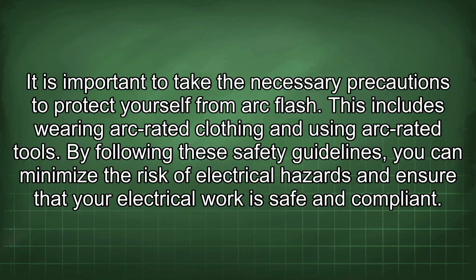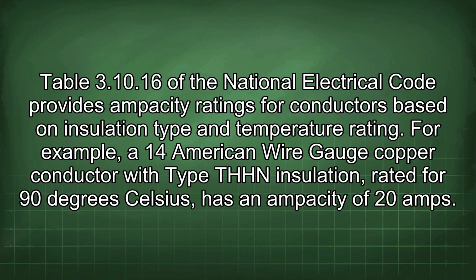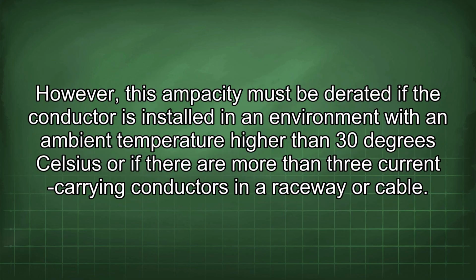safe and compliant. Table 3.10.16 of the National Electrical Code provides ampacity ratings for conductors based on insulation type and temperature rating. For example, a 14 American wire gauge copper conductor with type THHN insulation, rated for 90 degrees Celsius, has an ampacity of 20 amps. However, this ampacity must be derated if the conductor is installed in an environment with an ambient temperature higher than 30 degrees Celsius, or if there are more than 3 current-carrying conductors in a raceway or cable.